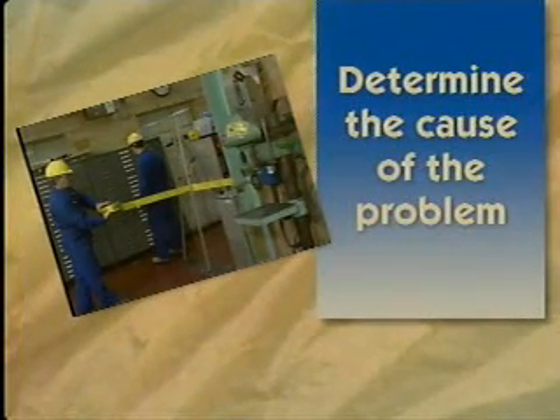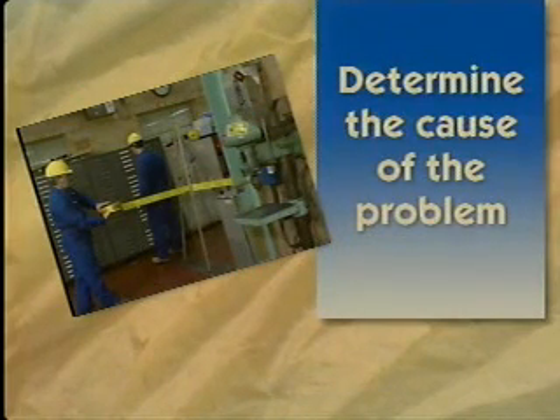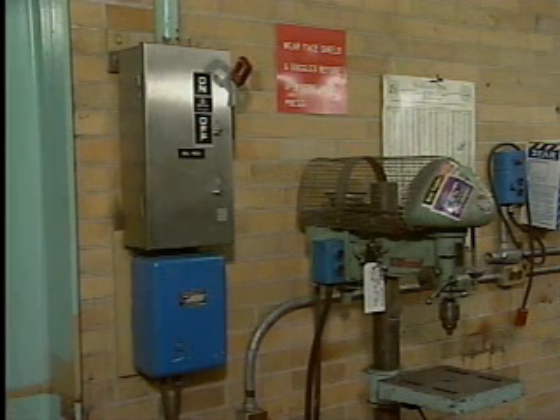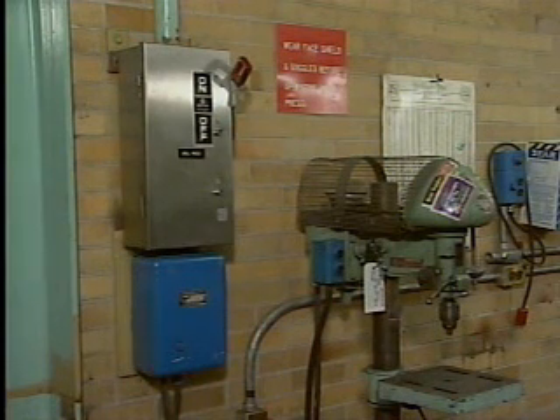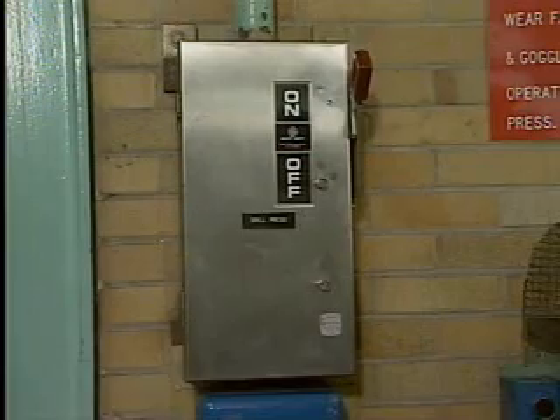With the work area secured, the electrician begins the next step of the troubleshooting procedure, which is to determine the cause of the problem. It's possible that the problem is just that the feeder for this circuit has been shut off elsewhere in the plant. Making sure that a circuit has proper voltage is usually a good place to start troubleshooting.